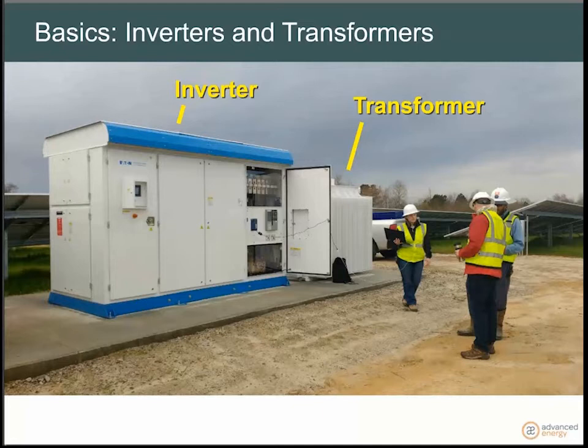To give you a frame of reference, the battery in your car runs at 12 volts DC. At a typical grid-scale solar facility, the panels are wired together to create about 1,000 volts DC. That solar voltage is then converted to 600 volts AC by the inverter, and commonly boosted by the transformer to around 24,000 volts AC for the grid. Needless to say, these are hazardous levels of electric power that require attention to all safety warnings and instructions.